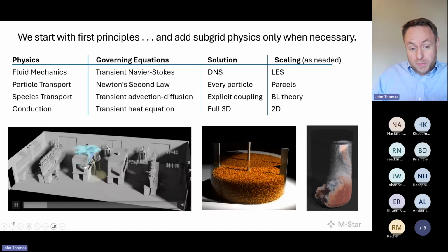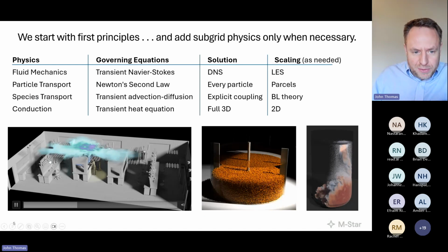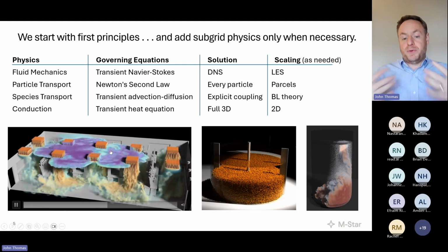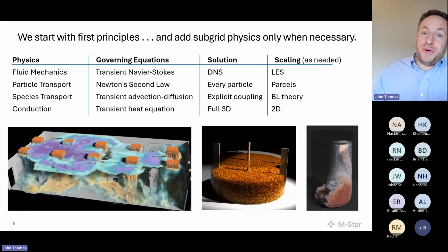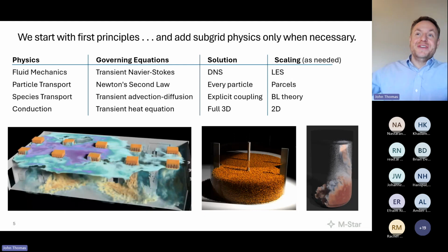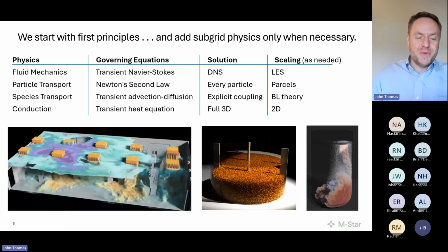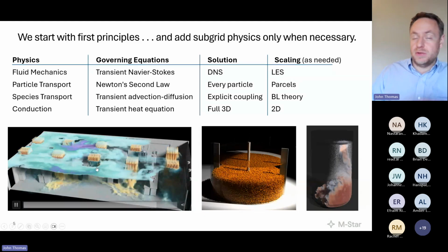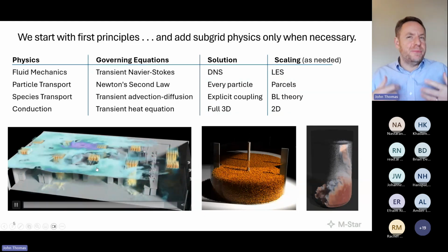And here, we'll speak to the system later on. We're modeling this physics in a time-accurate manner. Here's a little lab space. We have some sort of leak. Eventually, there's going to be a sensor here that detects that gas and then purges the room, or attempts to purge the room. This isn't a great purge because as part of this purge, we're just mixing the bad gas everywhere. We can do a much more intelligent purge by selectively turning on some of the inlets and outlets. But foundationally, this is in play now.